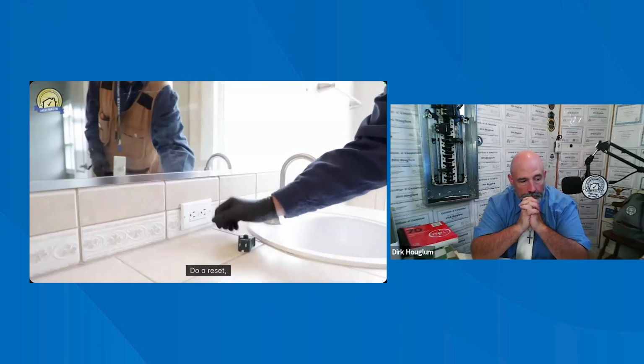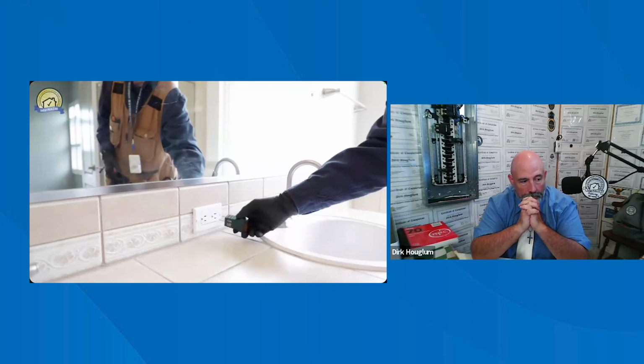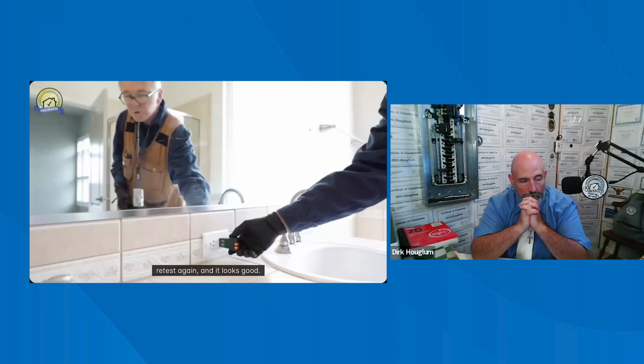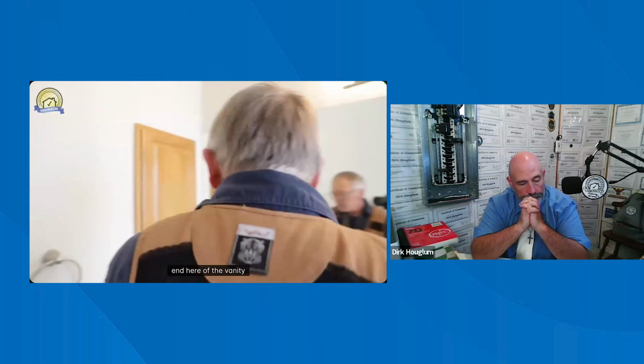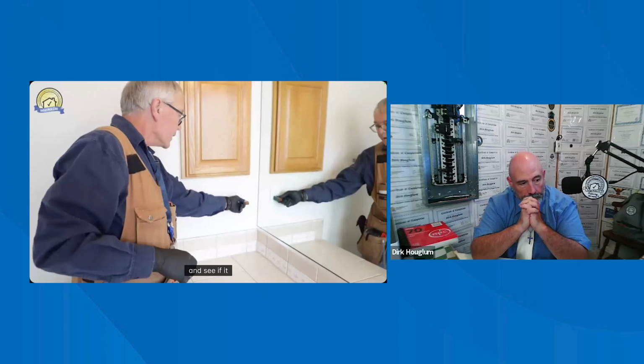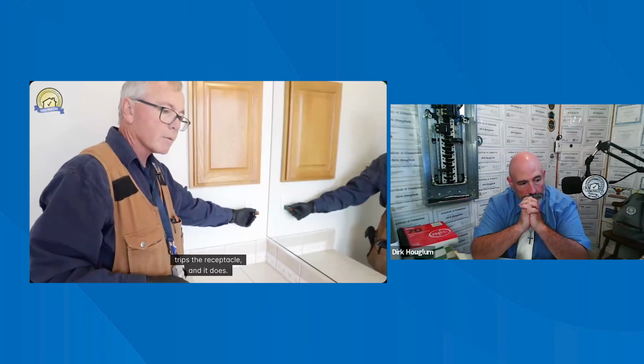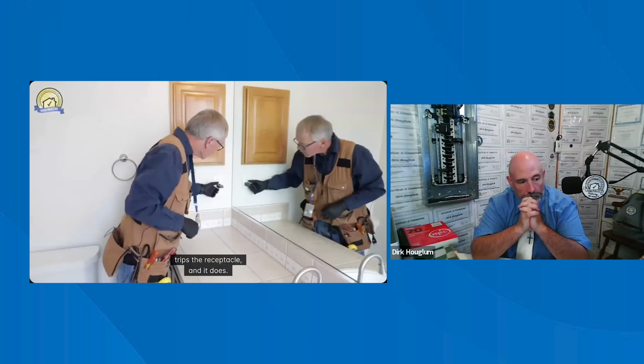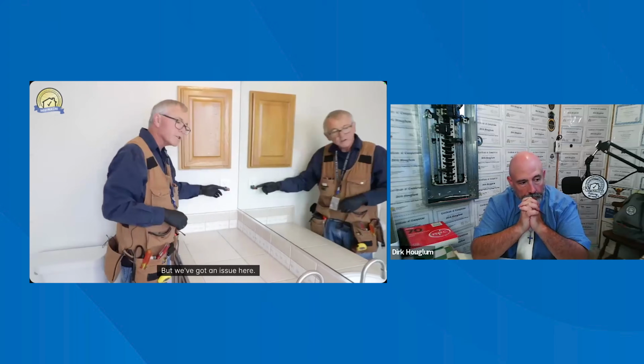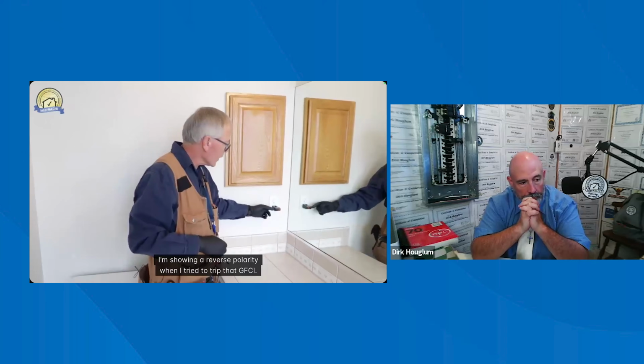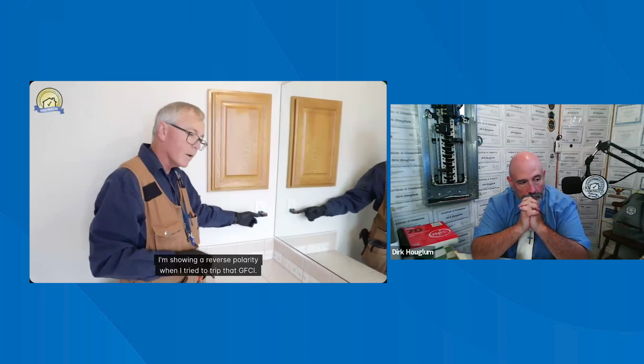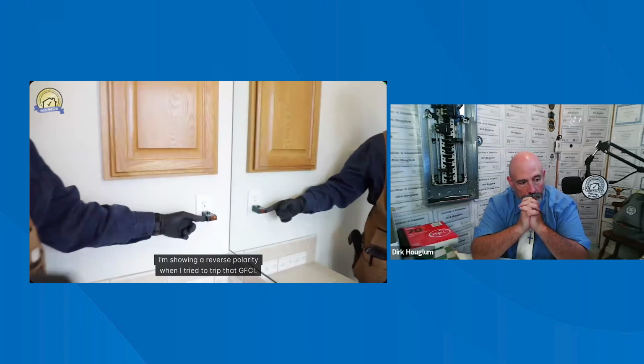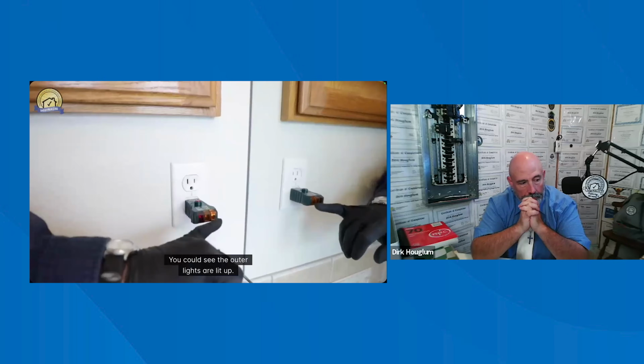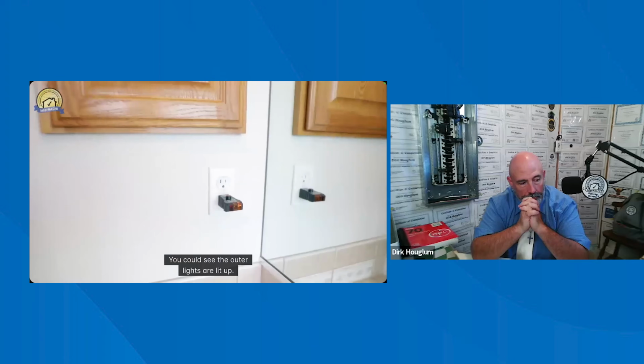We'll do a reset. Retest again, and it looks good. Now I'm going to move to the receptacle down on the other end of the vanity and see if it trips the receptacle, and it does. But we've got an issue here. I'm showing a reverse polarity when I tried to trip that GFCI. You can see the outer lights are lit up.